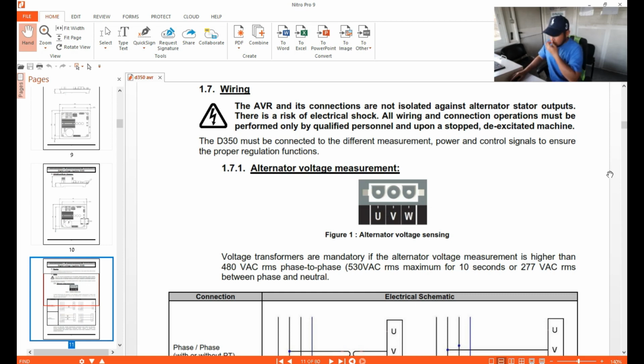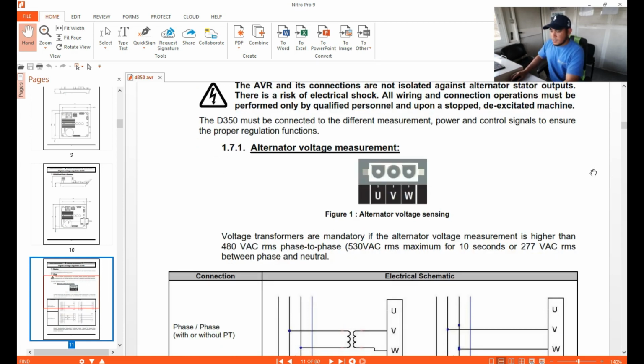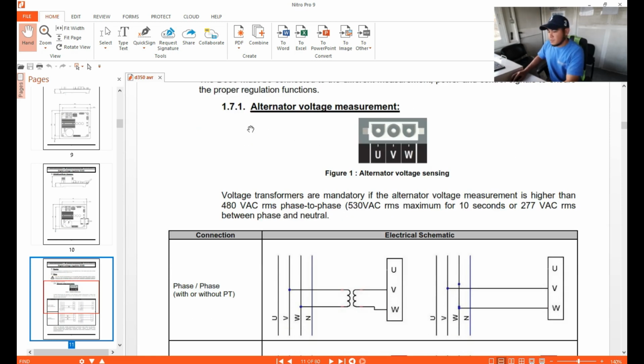Okay, so here, the D350 must be connected to the alternator for different measurements and power control signals to ensure proper regulation function. They have their own designated connections, and you can also modify the connections, depending on the functionality or the purpose of what you are doing. So here is the alternator voltage measurement. Here you can connect your UVW, which is the sensing input. So the alternator voltage sensing, that's what is stated here. This is the 3-phase sensing voltage.